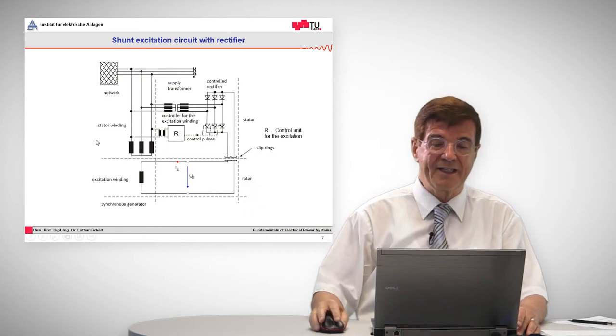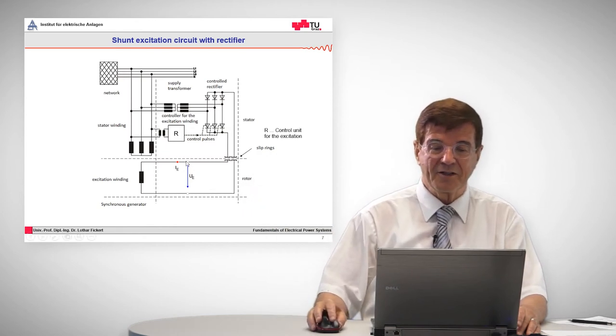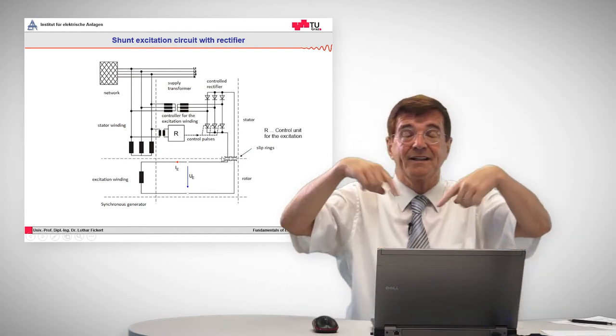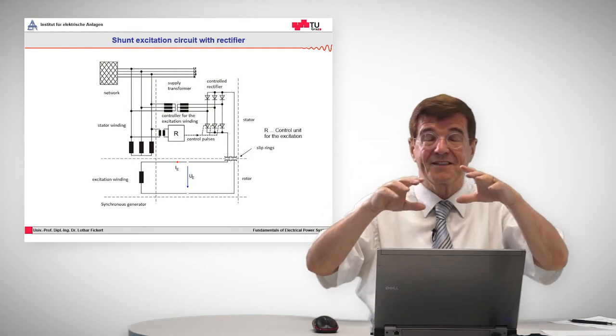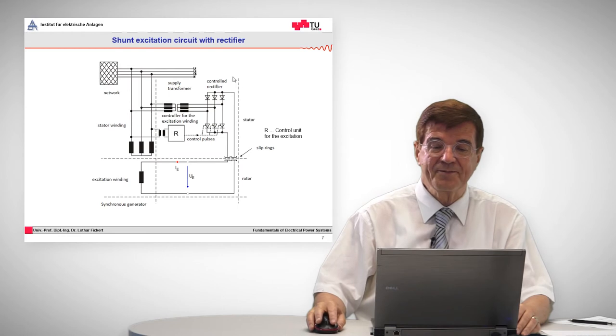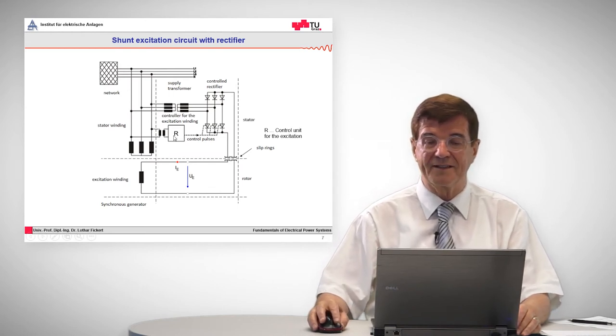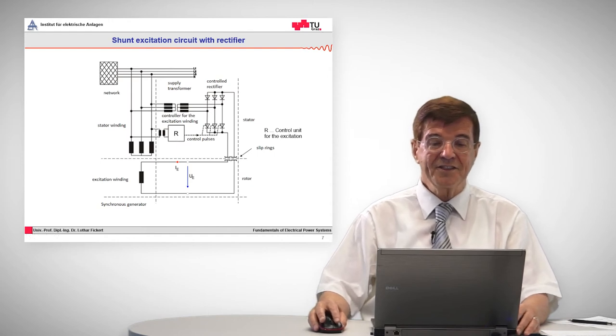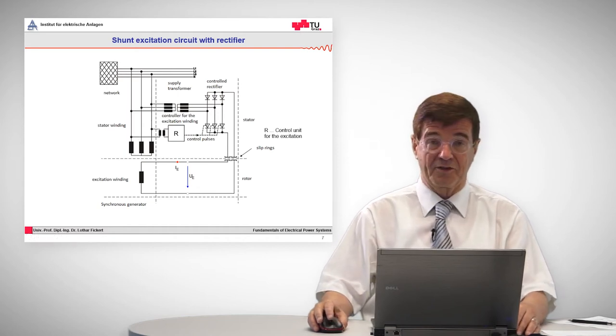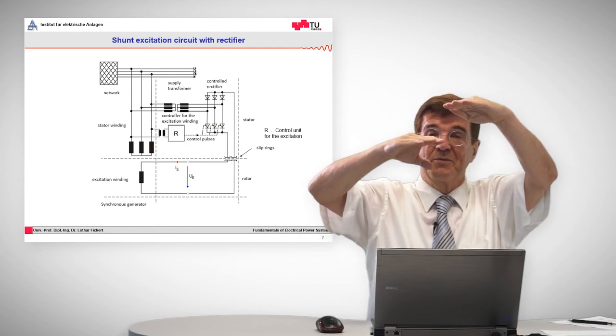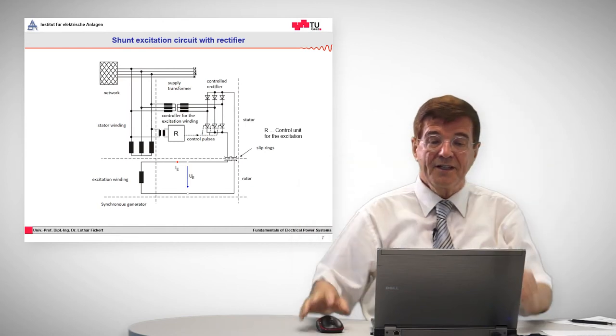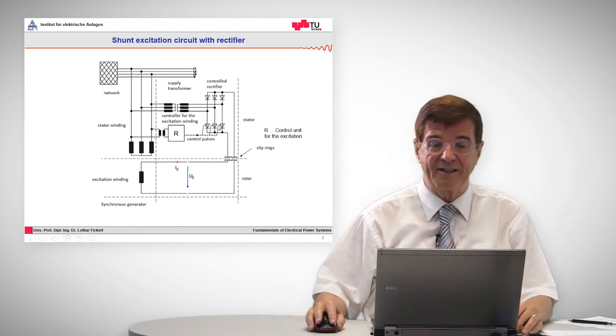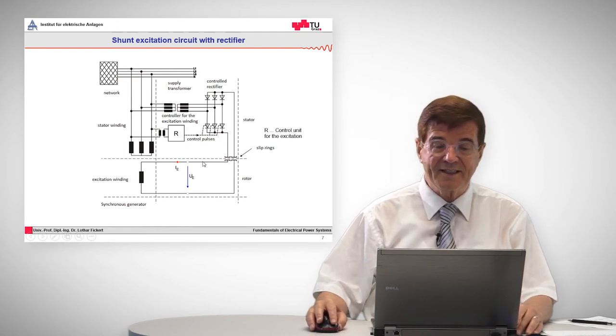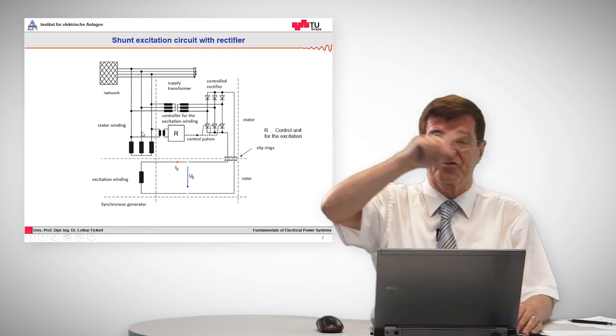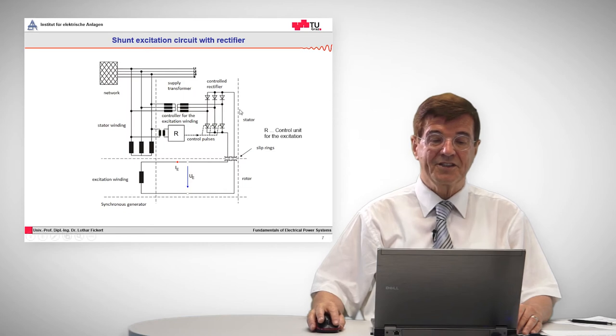Into technology, we see how this DC current, this exciter current, is produced. We go back, it comes through slip rings because it's a rotating device, and that must be provided with DC current. So this DC current goes through these so-called slip rings. It is produced by a rectifier bridge, which in turn is controlled by this control unit for the excitation. And that measures the phase-to-phase voltage of the output voltage of this generator. So that means if the output voltage of the generator is below its nominal value, this will be detected by the control unit, which in turn, by changing the firing angle of these thyristors, increases the DC current and in turn raises the output voltage. So this is a closed control loop which stabilizes the voltage.